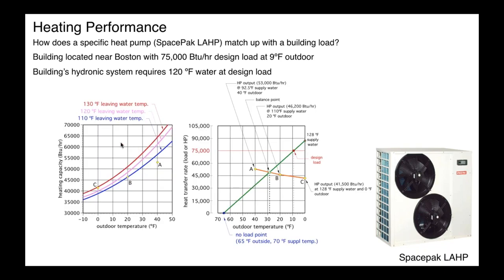So here's the capacity graphs. This is, again, heat pump BTU per hour output as a function of outdoor temperature and water temperature. And what I did, I just took 3 points, somewhat arbitrary. I took 1 point at zero outside, 1 point at 20, and 1 point at 40. And we looked at what the loads are in the building at that point, and then plotted a graph over here. So the green line, this represents the model that we're using for the simulated heating load. And you can see, again, design conditions correspond to 9 degrees outside, 75,000 BTUs per hour, okay? And I plotted those 3 points.